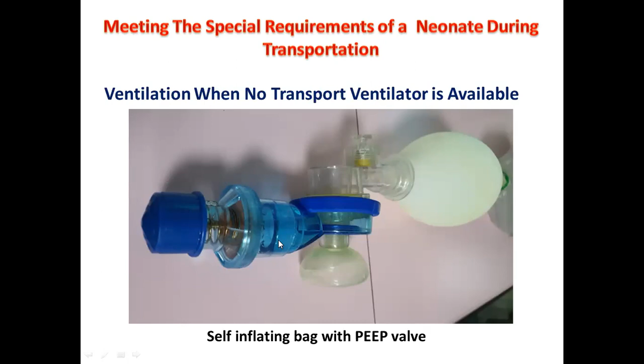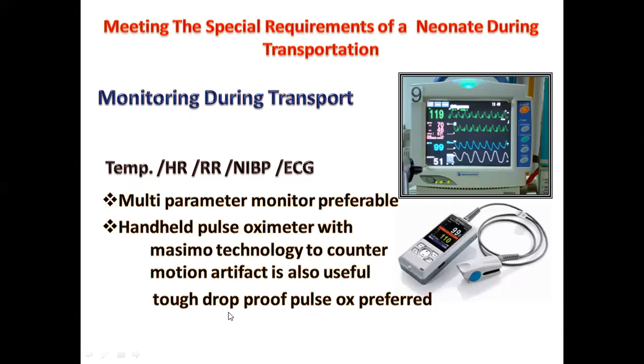Monitoring during transportation is very important. At least temperature, heart rate, respiratory rate, NIBP, and ECG if possible. So a multipara monitor is preferable, and a handheld pulse oximeter with Masimo technology is to be preferred, because when motion artifact is there, often we are not able to pick up good recordings, and often they keep on changing. Even if the baby is in shock, because of the Masimo effect, the pulse ox will pick up the pulsations. Drop-proof pulse oximeters are also preferred. Many companies are giving them; they show you, throw it and it doesn't break. So we prefer those in our ambulances.